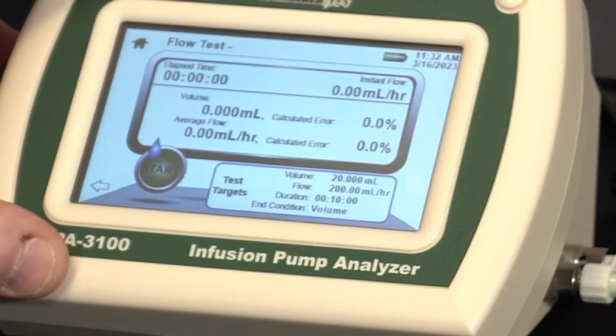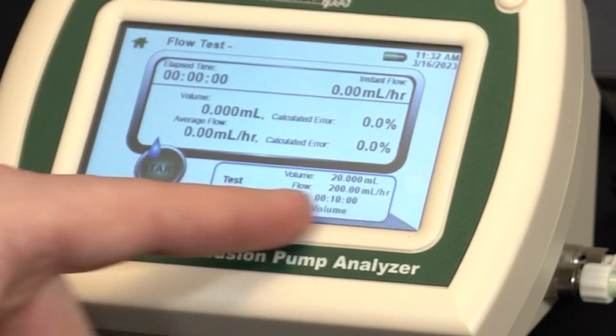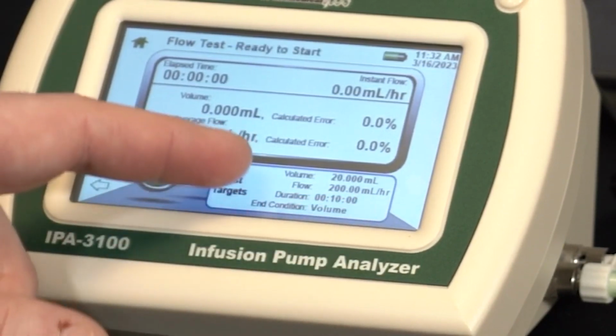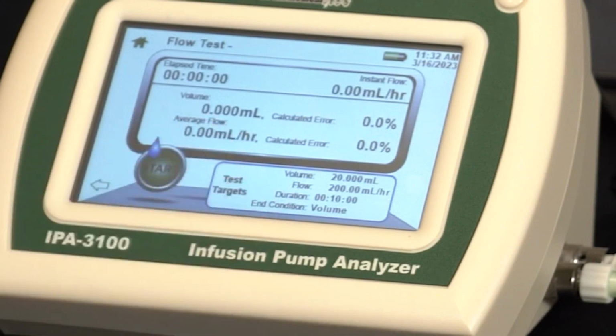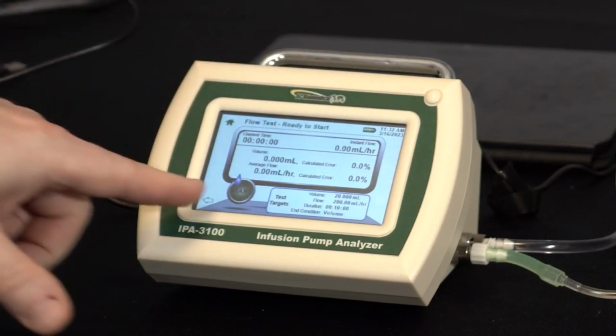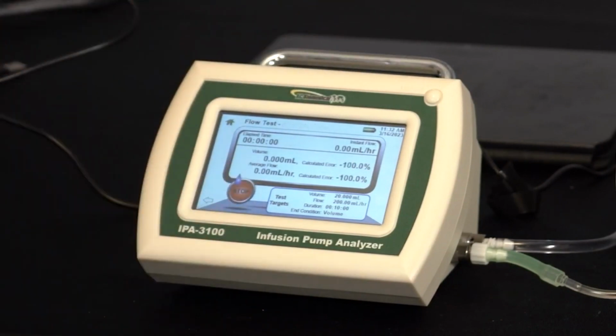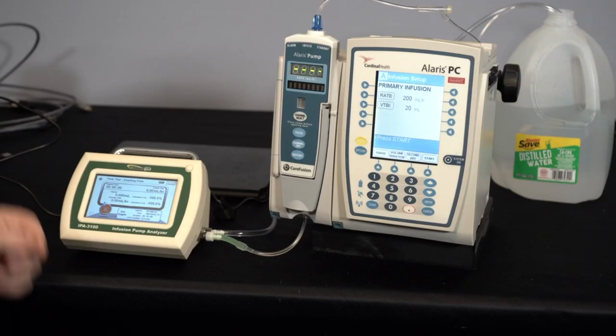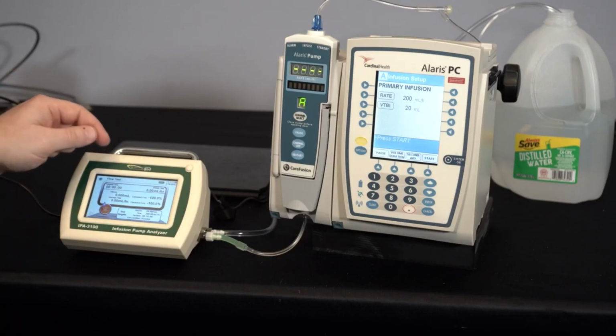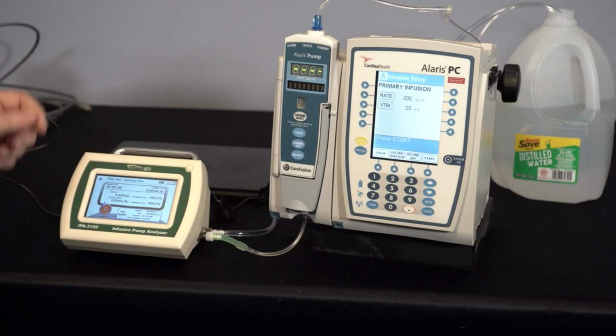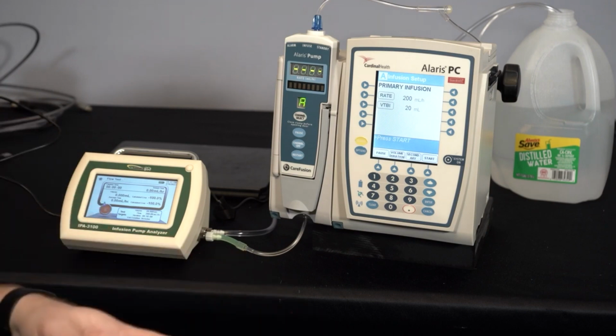The IPA 3100 screen shows me the configuration at the bottom. I've got my programmed volume, flow, duration, and end condition. At the top, it tells me that it's ready to start. And I have my start button right here. So all I have to do is press that, and now it's ready to start the test. It's waiting for the flow to begin. Once it detects flow, then it's going to start the time. If I had selected manual for the start mode, the timer would be running right now, and it would be accumulating time. And it calculates the flow rate by volume over time.